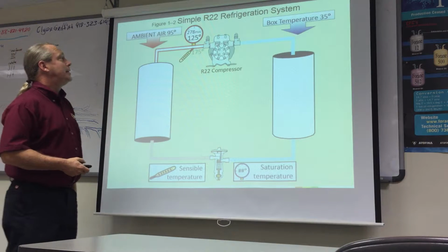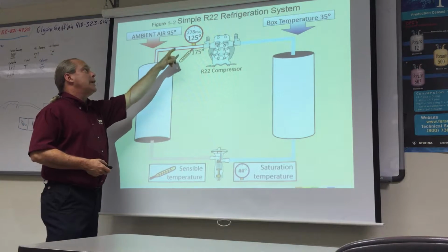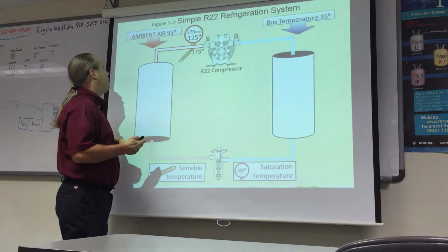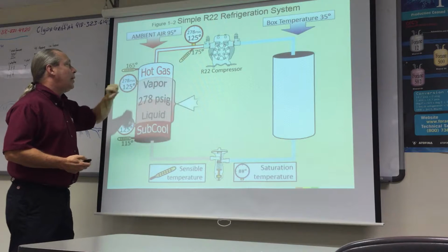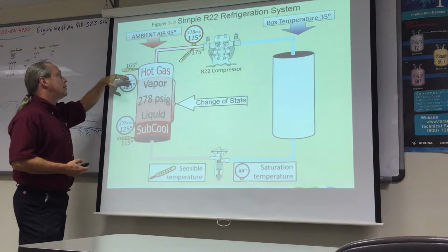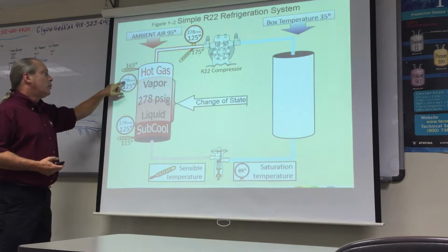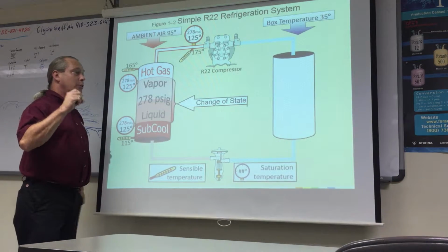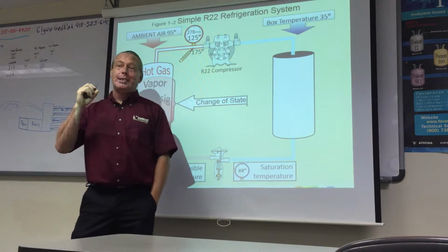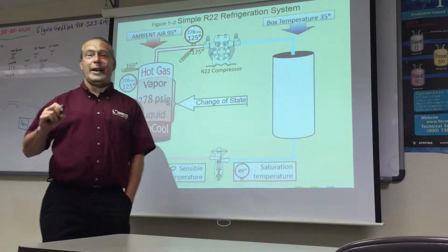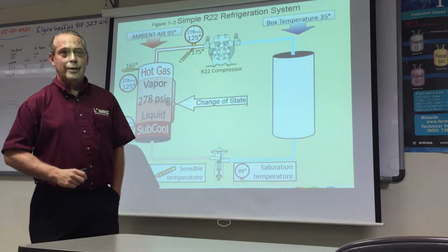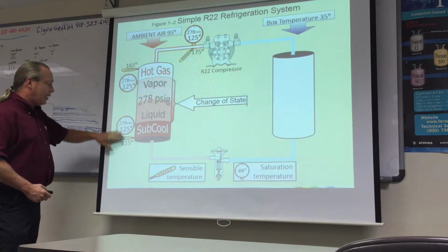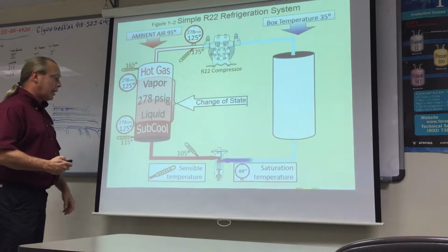We're coming out still 278, 125 degrees, coming out of the compressor at 175, cooling off by the time we actually get into the condenser at 165. We're at 278 psig, 125. You will notice that is the exact same temperature we came out of the compressor as. So let's continue. Same thing all the way down, even in the subcooling range.